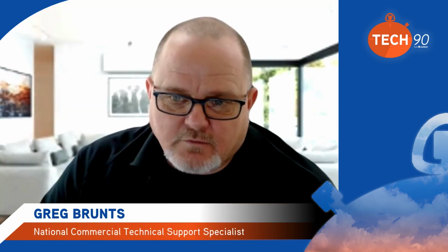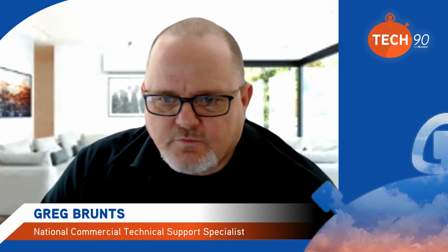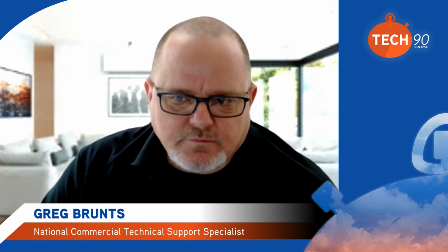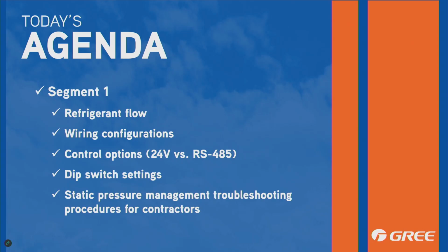So today we're going to be covering the FLEXX R32 installation and airflow. Our schedule today, first we'll run a clip from a recent training covering refrigerant flow, wiring configurations, control options for both 24 volt and using the GREE controller, which uses RS485. Dip switch settings for whether you're doing a 24 volt operation or you're doing RS485 operation. You do have to set the machine up to know what control you're using. So we're going to cover that.